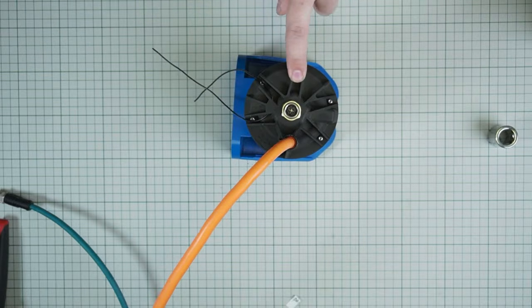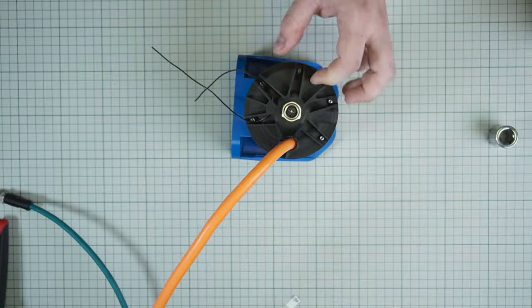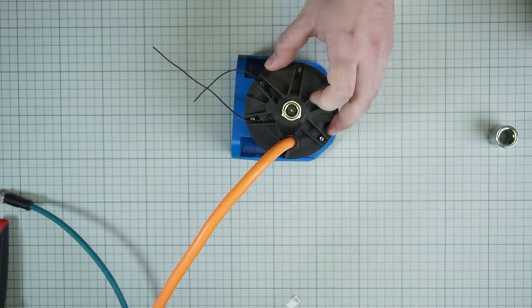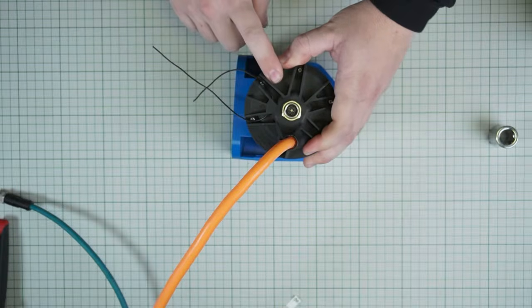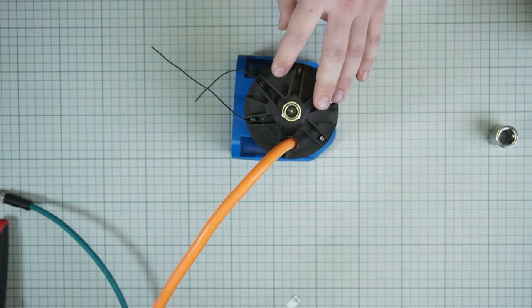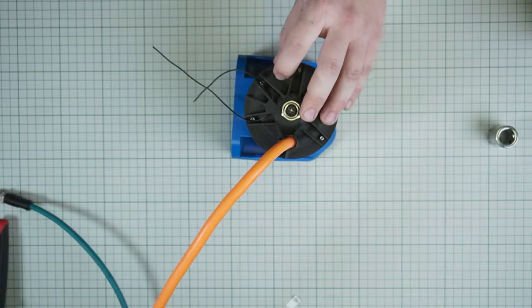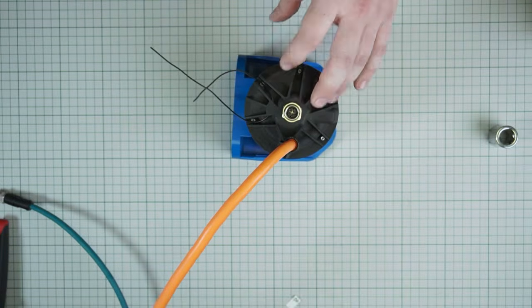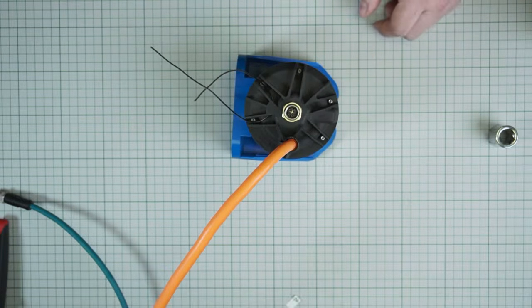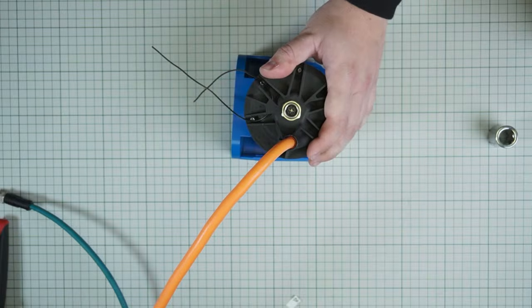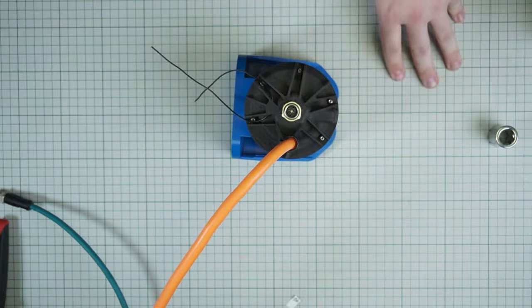I would also like to mention that for the positive locking, the tab washers are not necessary for the AC connections, because the cap of the motor is designed in a mindset that it doesn't let the bolts fully undo themselves if they are loosening up. So you don't need to do positive locking here. This is by design guaranteed, it's working as expected.